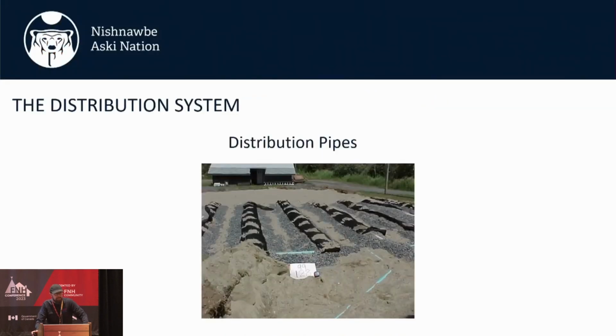So when I started in the septic system world, I was dealing with a lot of distribution pipes wrapped in 15 centimeters of stone underneath. Typically you had a 3 or a 4 inch pipe and then 5 centimeters of stone over top and then a geotextile fabric over top of that. Since those times, a lot has changed. This is still a very reasonable way of doing things. It's just quite labor intensive, and I know that in a lot of communities, granular and aggregate is just not a real thing.